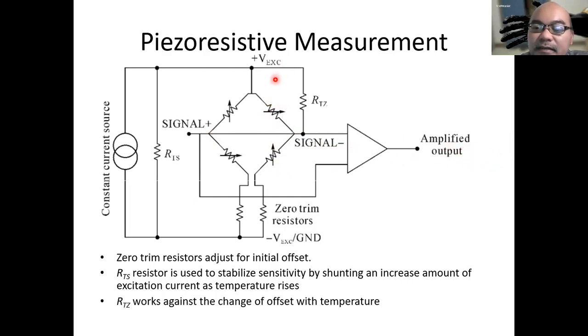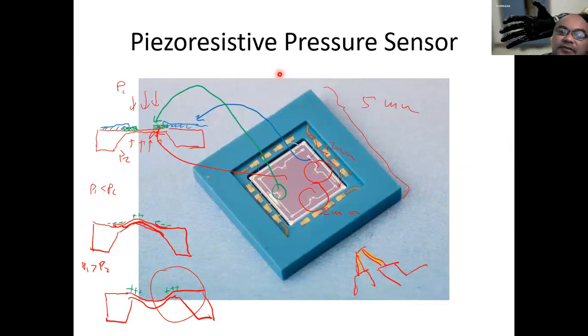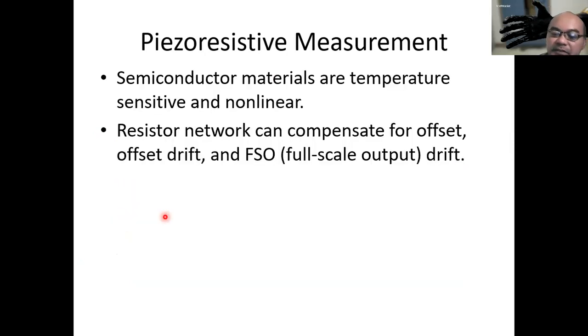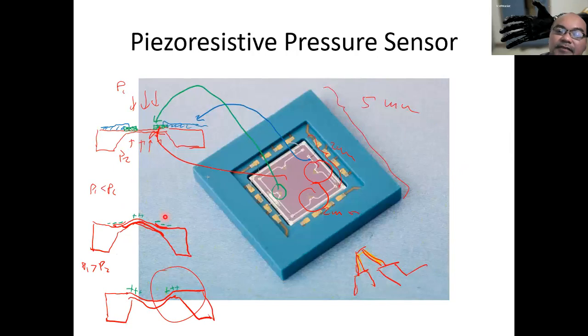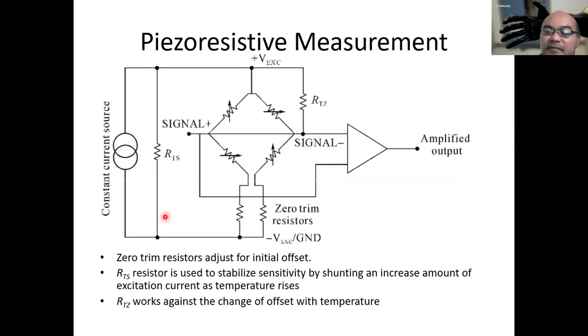But when there is resistance change, when there is pressure, for example, as shown here, P1 is less than P2, the diaphragm will bulge, right? And the four piezoresistive devices will feel negative strain or compression. If the gauge factor is positive, then the resistance will decrease. All four resistors will decrease, and we will feel all four amplified as amplified voltage here.